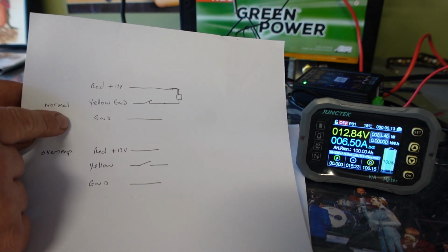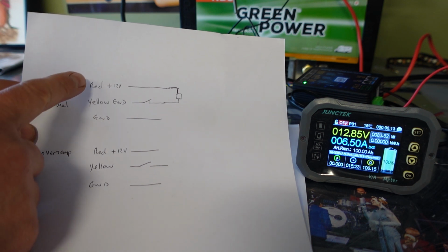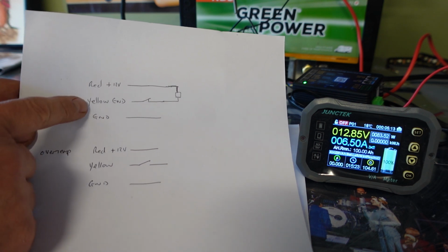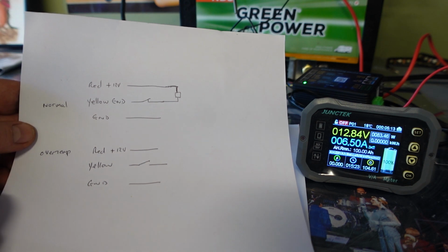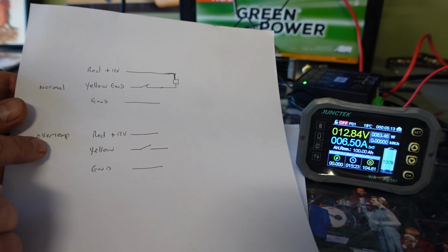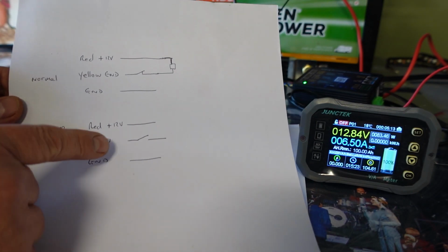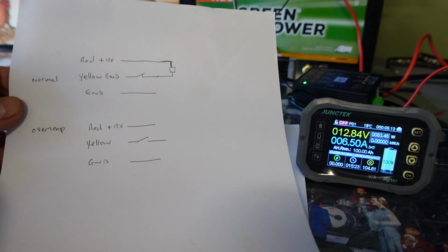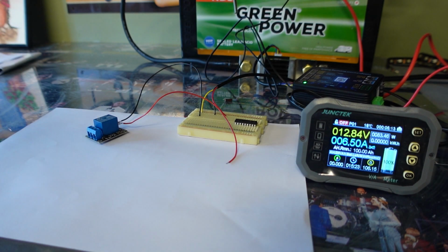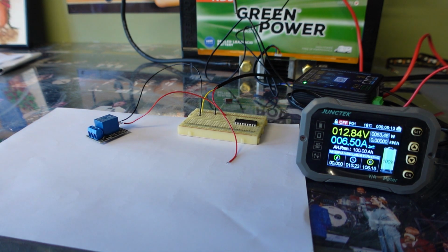So in normal conditions, when everything's working fine, you'd have 12 volts out in the red, yellow in the ground to a relay, and the relay would be on all the time. When it goes into a protection, like an over temp section, the yellow ground would open up and then the relay drops out. So it's quite simple. The only downside with that is that the relay's on all the time, which means it gets hot.